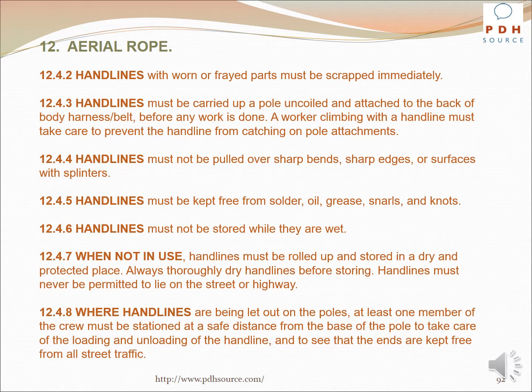Hand lines with worn or frayed parts must be scrapped immediately. Hand lines must be carried up a pole uncoiled and attached to the back of body harness belt before any work is done. A worker climbing with a hand line must take care to prevent the hand line from catching on pole attachments. Hand lines must not be pulled over sharp bends, sharp edges, or surfaces with splinters. Hand lines must be kept free from solder, oil, grease, snarls, and knots.